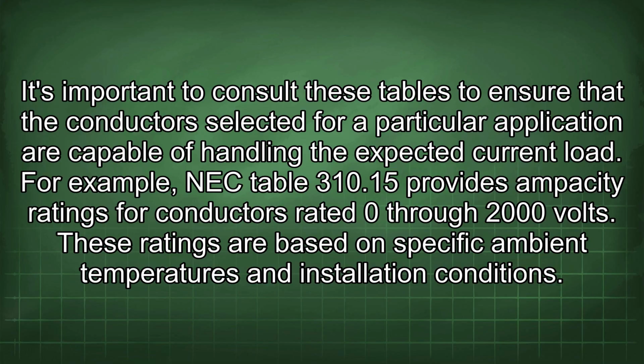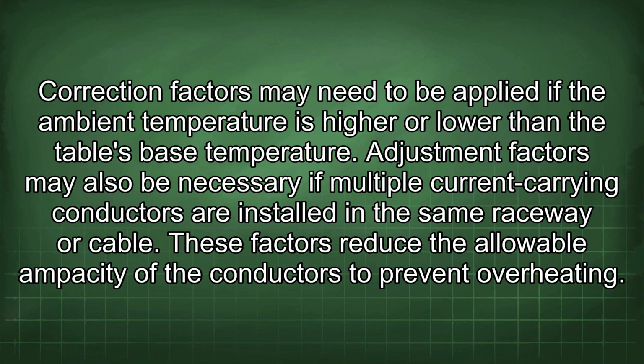For example, NEC Table 310.15 provides ampacity ratings for conductors rated 0 through 2000 volts. These ratings are based on specific ambient temperatures and installation conditions. Correction factors may need to be applied if the ambient temperature is higher or lower than the table's base temperature. Adjustment factors may also be necessary if multiple current-carrying conductors are installed in the same raceway or cable. These factors reduce the allowable ampacity of the conductors to prevent overheating.